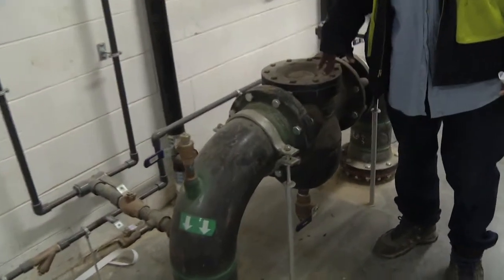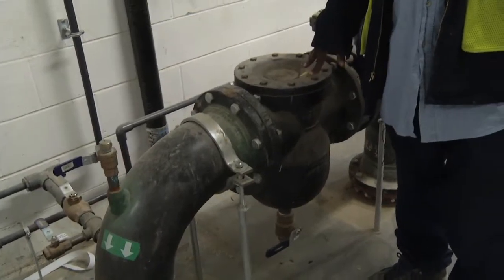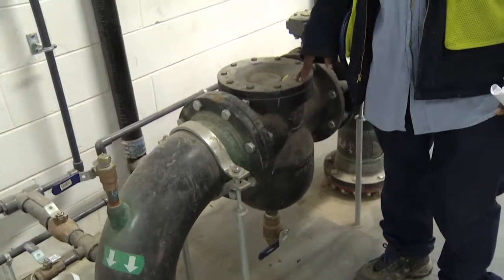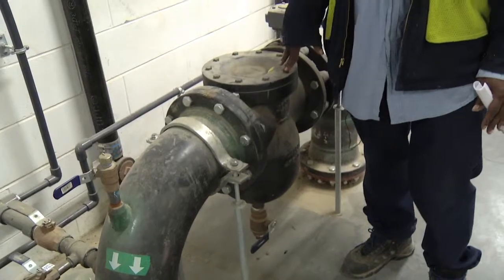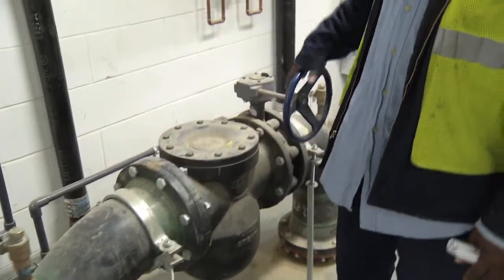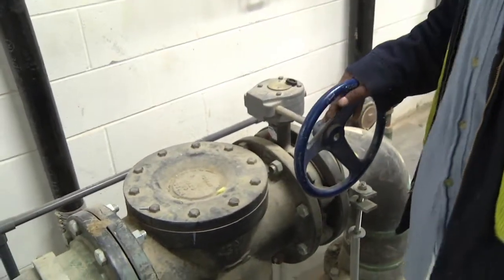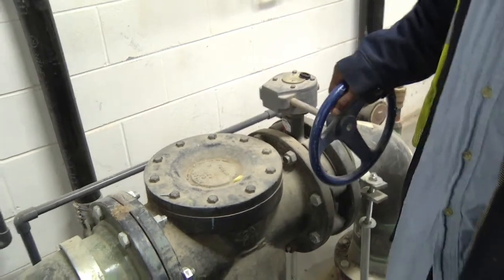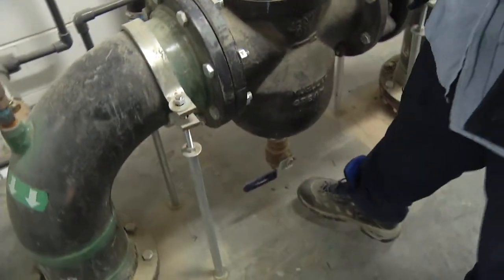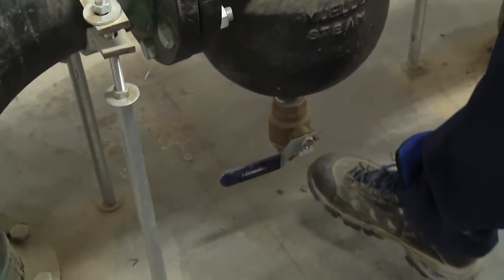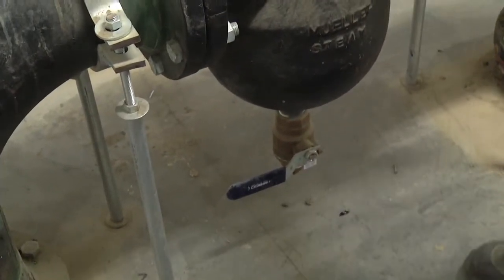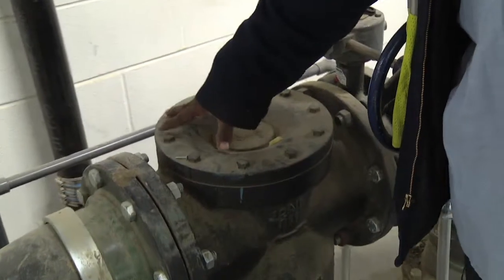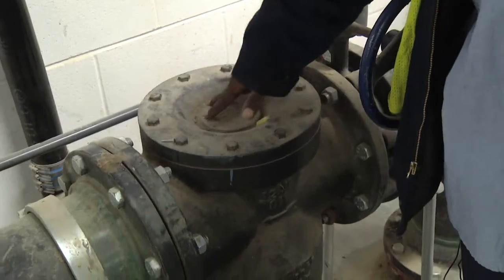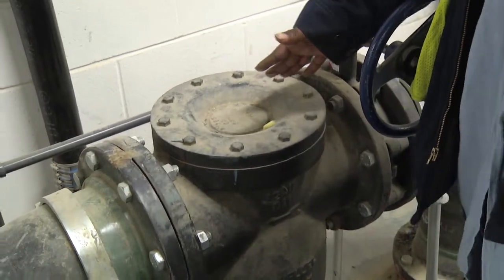Okay, strainers. This is a bucket strainer coming off of your cooling tower loop. I want to get into how you would clean it and when you would clean it. Basically what you would do, you would shut your valve off, you would kill water flow going through this valve. You would then attach a hose to your ball valve, empty your water out, take these bolts out here, and there's a basket in there that you take out and clean. And this is normally done annually.